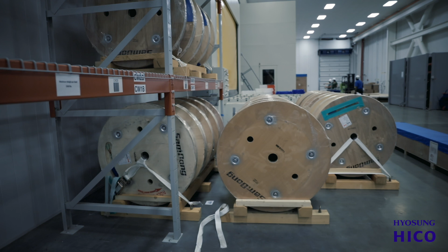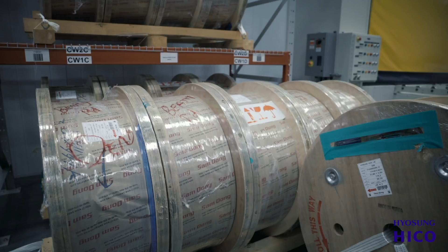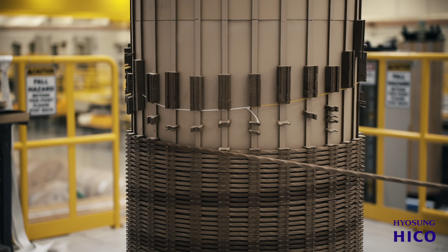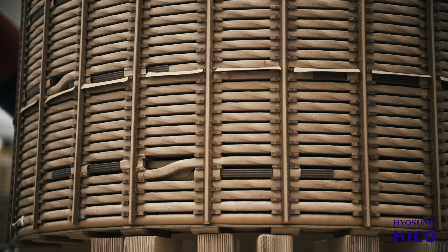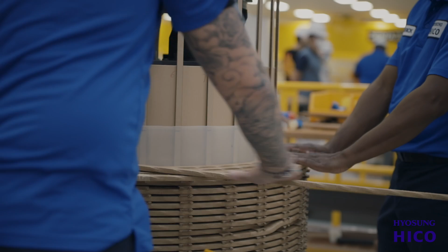It starts with preparation, starting from the cylinders and insulation parts. From there, get your conductor ready, loaded up on the spools for the conductor holders. Then you prep the wire, get it ready, run the wire to the mandrel itself, and then start winding. In the winding, there are different steps such as inside transpositions, outside transpositions, and applying the R spacers when needed per section. Once we complete the winding, after all the transpositions and additional processes, we check the lower half of the winding. Once we get to 100% of the lower half, we check again. Once that's all done, we do acid dipping on the ones that require it. At that point, we're ready to hand off to the marrying area, the phase assembly guys.